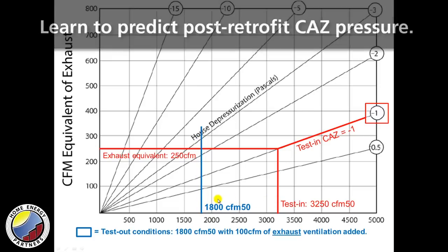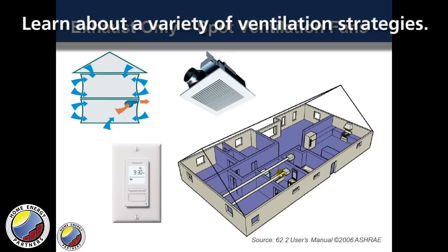This can be used to provide the whole building ventilation, or that portion of ventilation that's diluting the inside air. So in order to use an exhaust fan for a whole building ventilation need, you have to have a control that keeps track of how often that fan turns on and off.